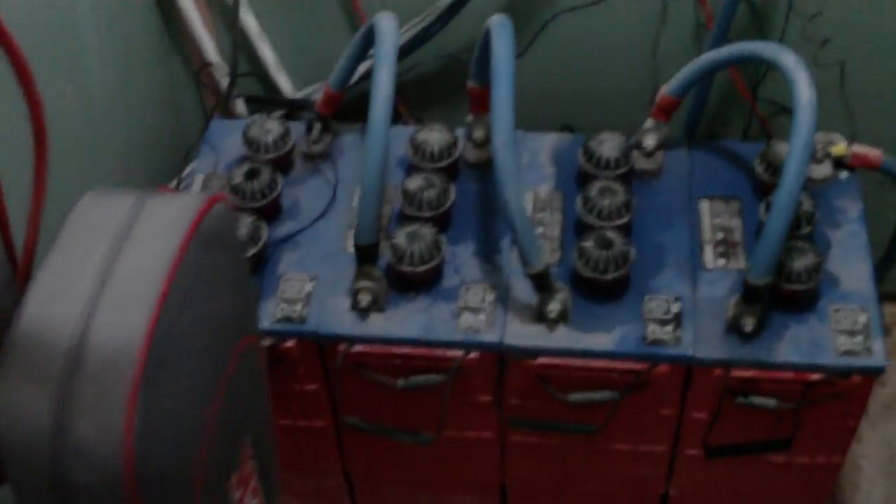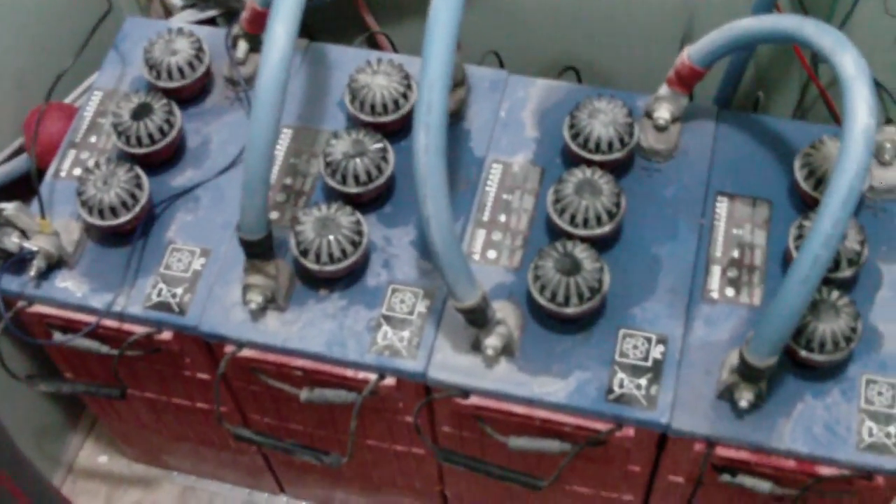This is the battery room — or utility room door, I guess you could call it. In here we have the wind turbine controller, the inverter, and that's where the solar panels come in. Power comes in from the solar panels or the wind turbine into these batteries. These are 6-volt batteries in a 24-volt system — each battery is 530 amp hours. From the batteries it goes back up into the inverter charger, then into the power panel which feeds everything in the house. That's the on-demand hot water heater — runs on propane, uses about one five-pound can every three weeks.